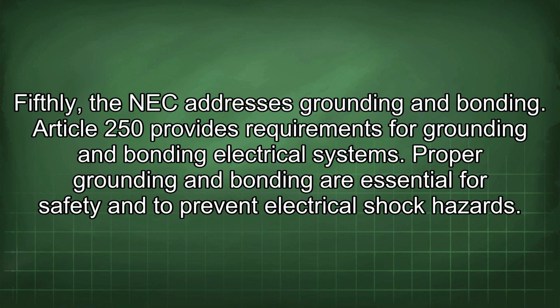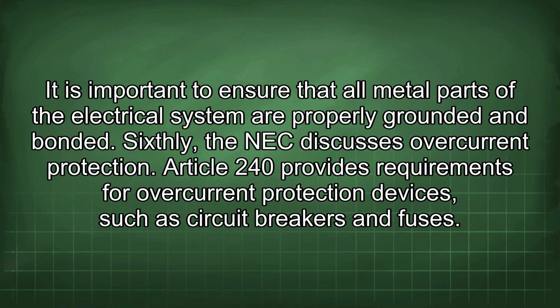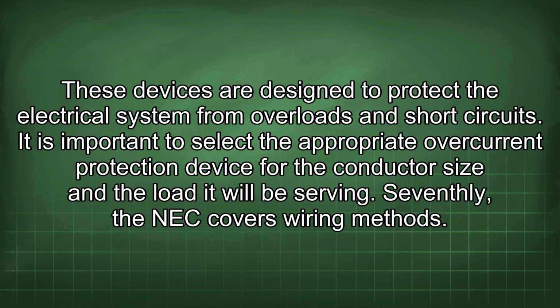Fifthly, the NEC addresses grounding and bonding. Article 250 provides requirements for grounding and bonding electrical systems. Proper grounding and bonding are essential for safety and to prevent electrical shock hazards. It is important to ensure that all metal parts of the electrical system are properly grounded and bonded. Sixthly, the NEC discusses overcurrent protection. Article 240 provides requirements for overcurrent protection devices, such as circuit breakers and fuses. These devices are designed to protect the electrical system from overloads and short circuits. It is important to select the appropriate overcurrent protection device for the conductor size and the load it will be serving.